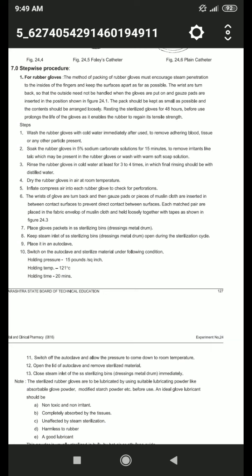First, wash the rubber gloves with cold water immediately after use to remove the adhering blood, tissue and any other particles present. Then soak the rubber gloves in 5% sodium carbonate solution for 15 minutes. Then, to remove irritants like talc which may be present in the rubber gloves, wash with a warm soft soap solution. Then rinse the rubber gloves in cold water at least 3 to 4 times. The final rinsing should be with distilled water.